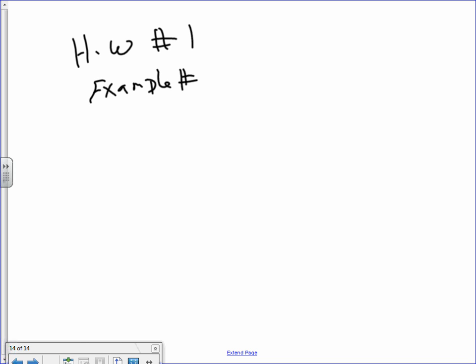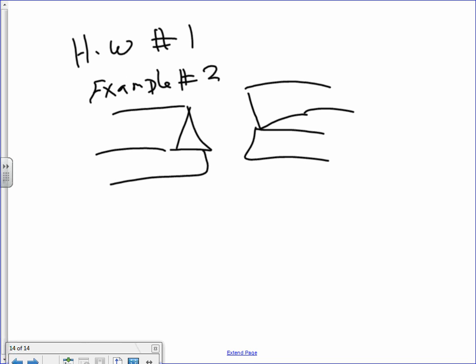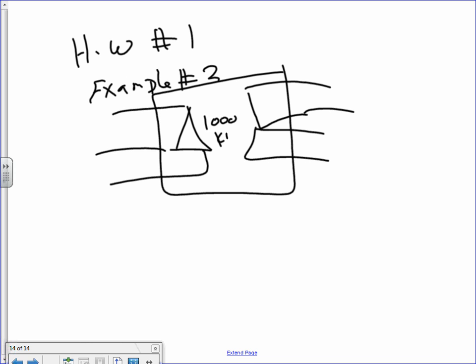example number 2. All you have to do is, here's a primary, here's a secondary. You guys are going to size the same thing for these. The only thing I'm going to give you is this one is going to be 1000 kVA. The primary is going to be a 4160. Oh no, 13.8. Let's use this one, 13.8. The primary is 13.8 kilovolt. The secondary, I would like you to use this one, guys, on 600 volt. Size, what do you need to size? Size the 5 things. Everybody knows what the 5 things are that we need to size? The conductors, the fuses, the grounding and bonding.